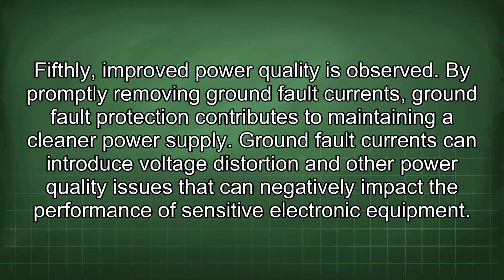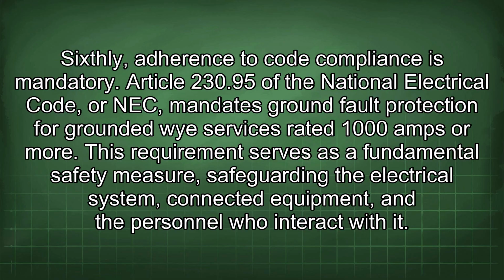Fifthly, improved power quality is observed. By promptly removing ground fault currents, ground fault protection contributes to maintaining a cleaner power supply. Ground fault currents can introduce voltage distortion and other power quality issues that can negatively impact the performance of sensitive electronic equipment. Sixthly, adherence to code compliance is mandatory.